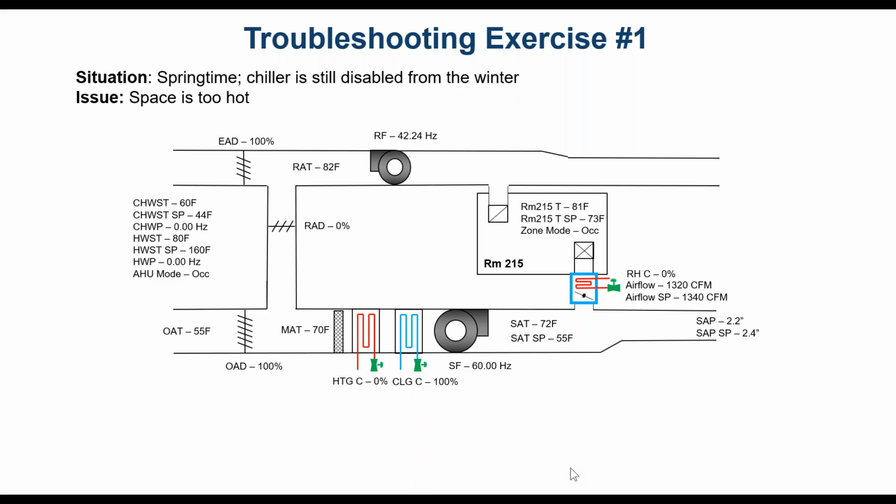All right, now I've also made 2 other handouts available to you, or 3 handouts in total. The sequence of operation slide has been made available to you, the troubleshooting exercises key information slide has been made available to you, as well as that 6-step methodical troubleshooting approach. So we're going to walk through that methodical troubleshooting approach now. So step 1, again, it's a prerequisite to know the sequence of operation for the system we've been working with.